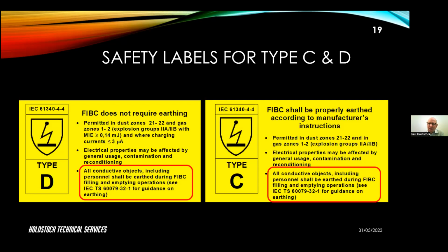The purpose of the testing is to make sure that at that point, where you still have some residual charge, there's not enough charge to cause ignition, and that's what you do with testing. But because you have some residual charge and some residual field, any nearby conductor, a person or any metal plant, for example, if it's isolated, can have charge induced onto it. So it's important still to make sure that any conducting objects are earthed.